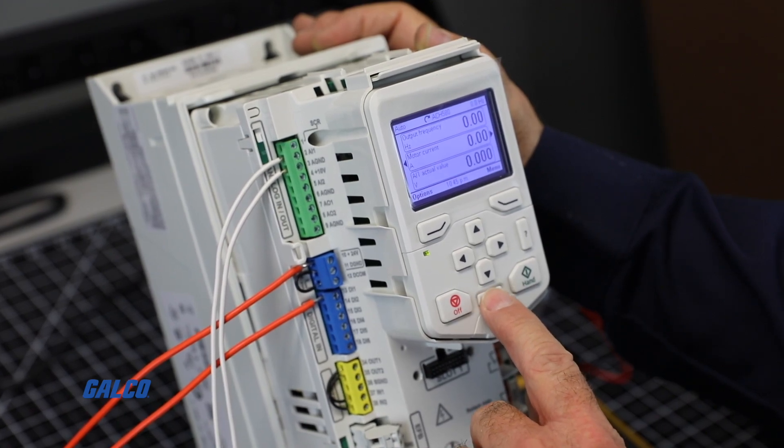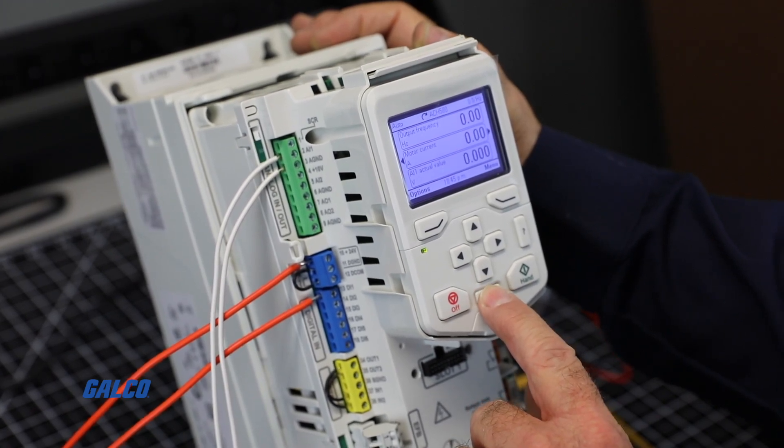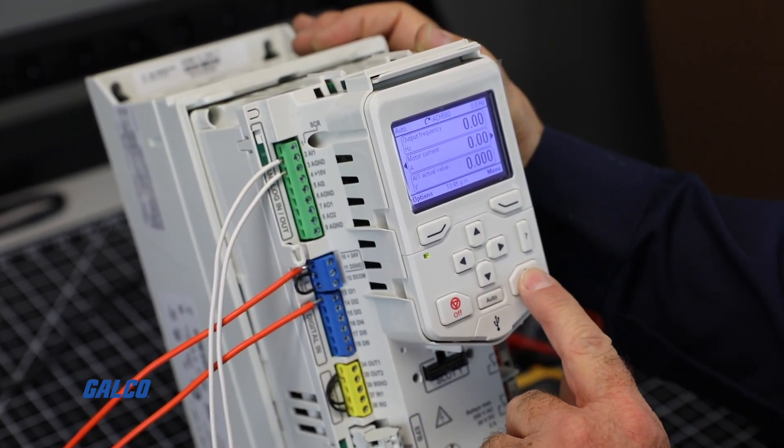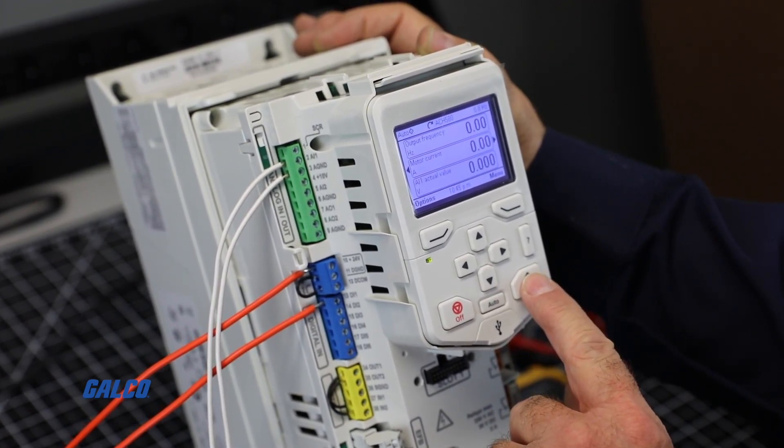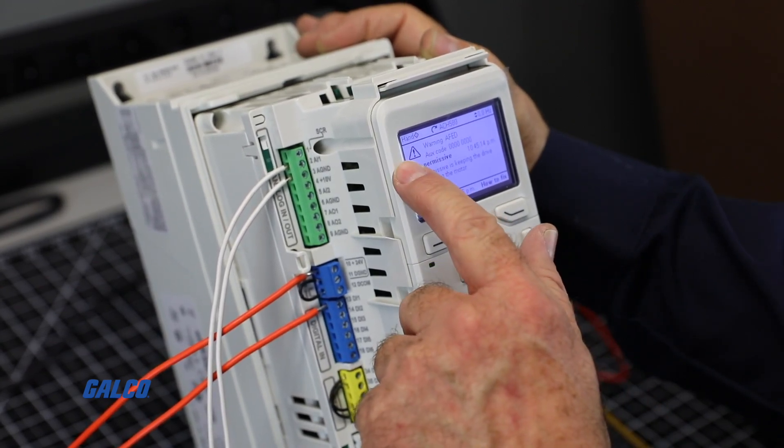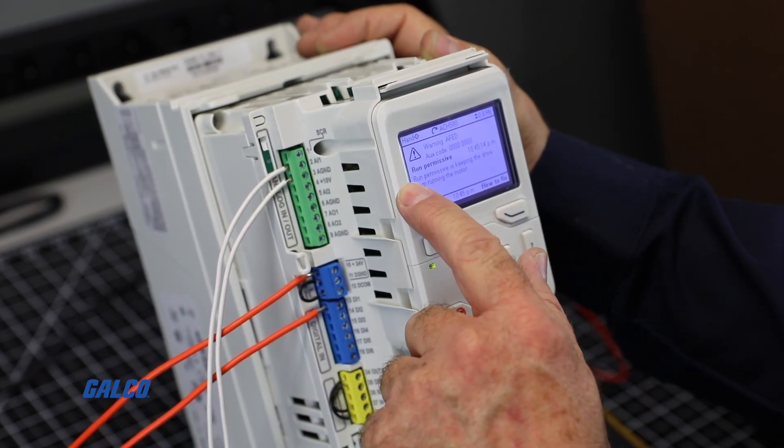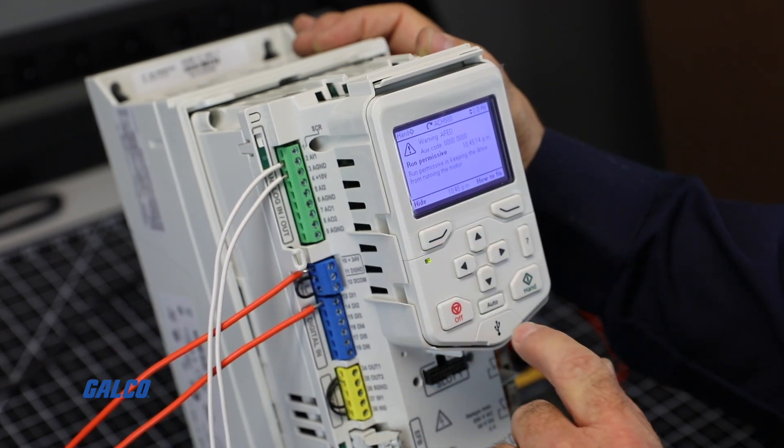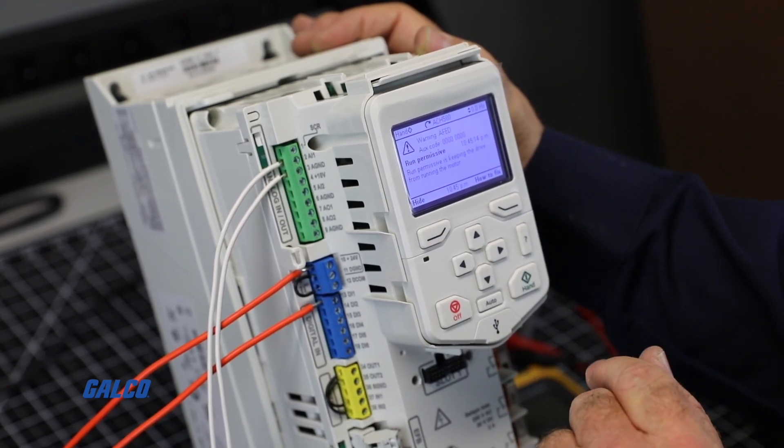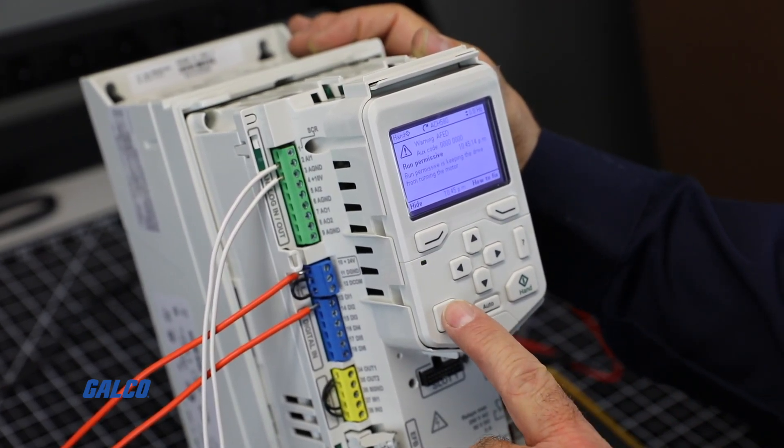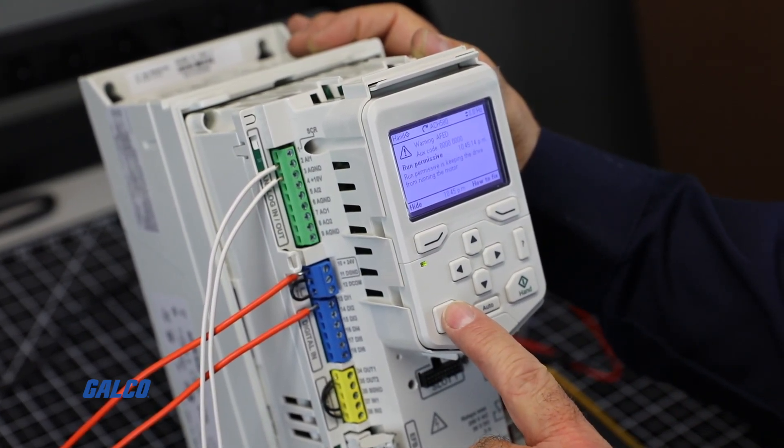To put the drive in non-local mode, push the Local Remote button on the face of the keypad between the Start and Stop buttons and follow the on-screen instructions. A fault will pop up saying that the Run Permissive is keeping the drive from running the motor.